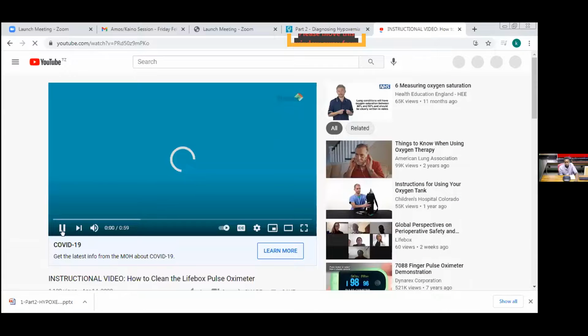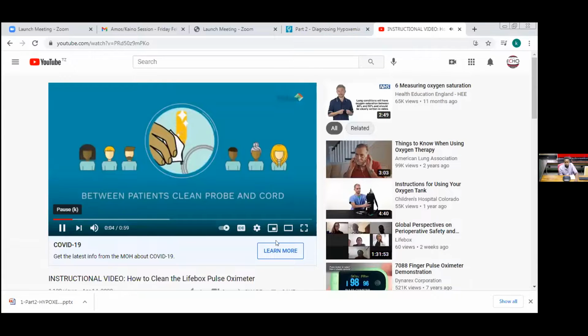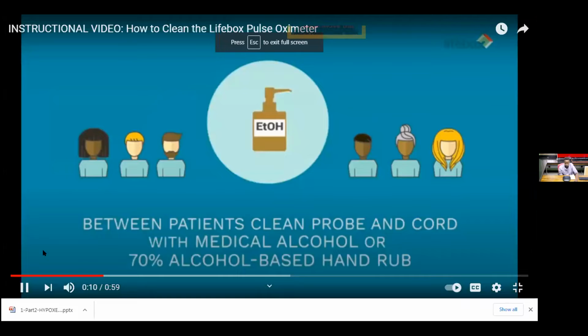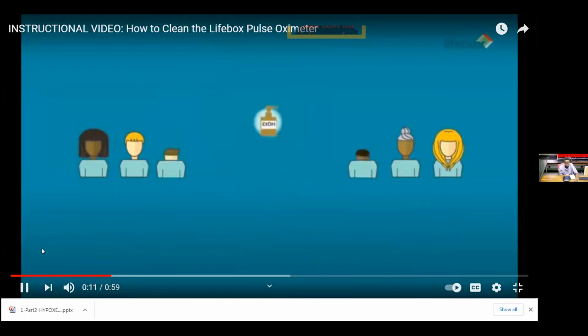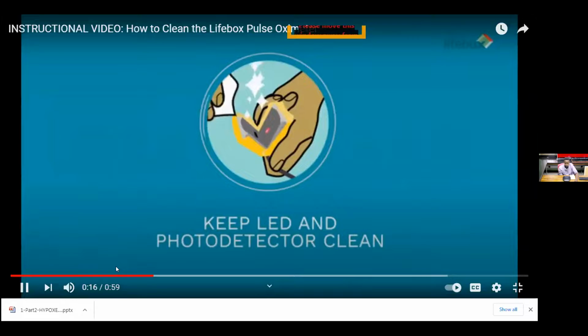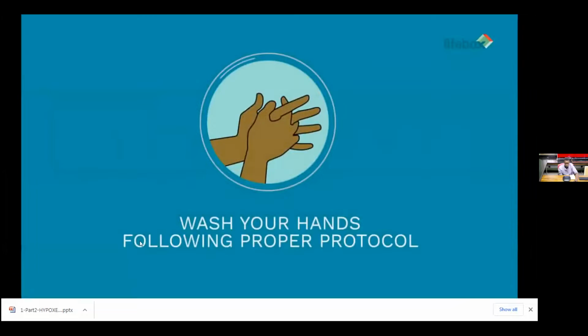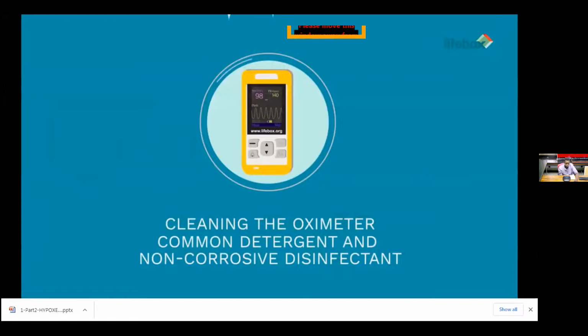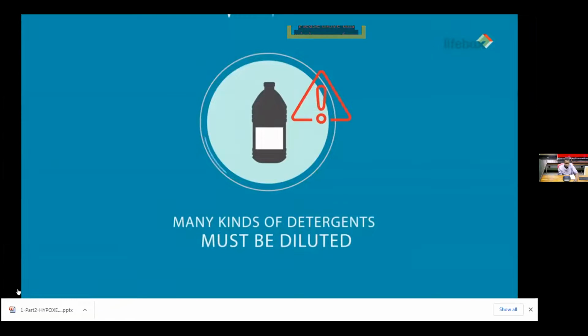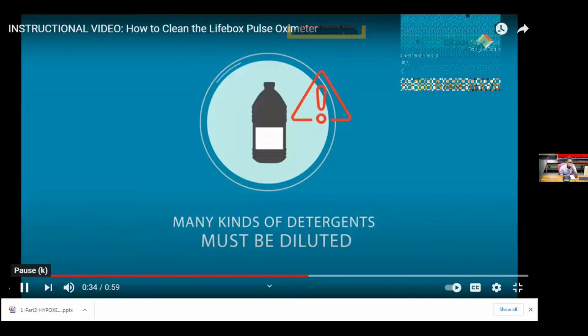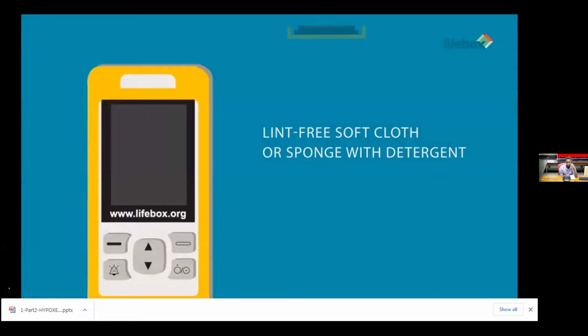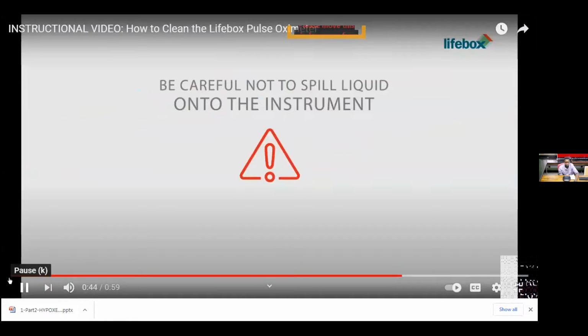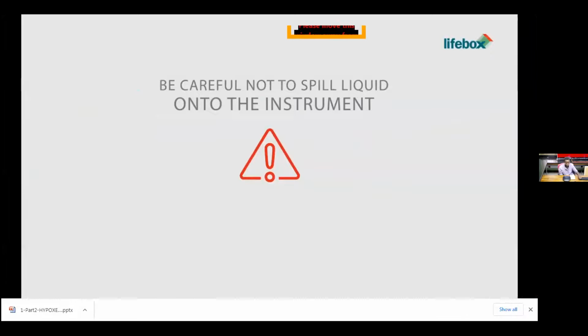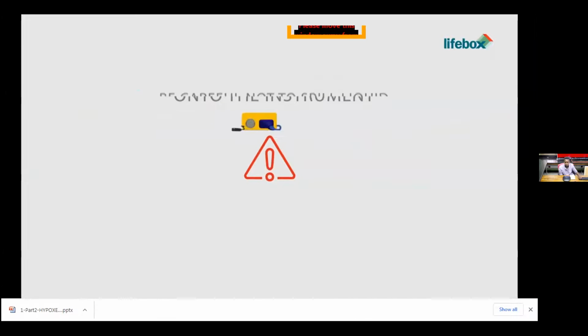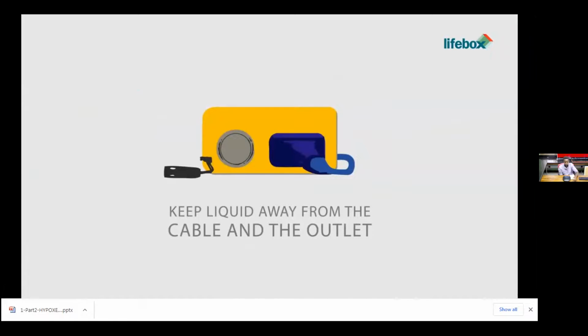Between patients, it is essential that you gently clean the probe and cord with medical alcohol. Small amounts of 70% alcohol-based hand rub will also work, but should be applied sparingly. It's important to keep the LED and photo detector clean. Please also remember to wash your hands, following proper protocol between patients. The oximeter should be wiped down regularly, using common detergent and non-corrosive disinfectant, such as those used in hospitals. Be aware that many kinds of detergents must be diluted prior to use. The oximeter case and screen can be wiped with a lint-free soft cloth or a sponge moistened in detergent. While cleaning the oximeter, be careful not to spill liquid onto the instrument and do not allow any liquid to spill inside the oximeter. When wiping the side panel of the oximeter, be especially careful to keep liquid away from the cable and the outlet.